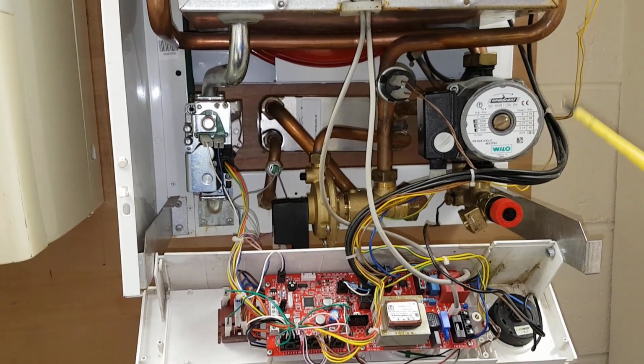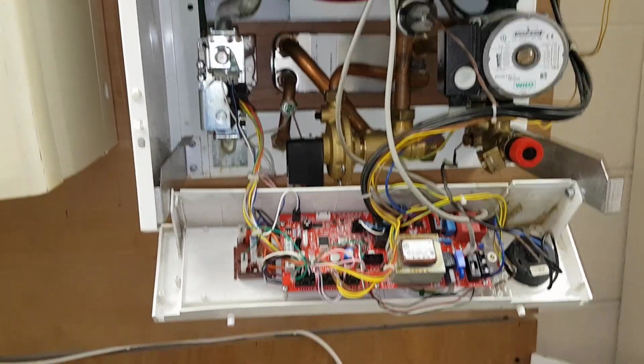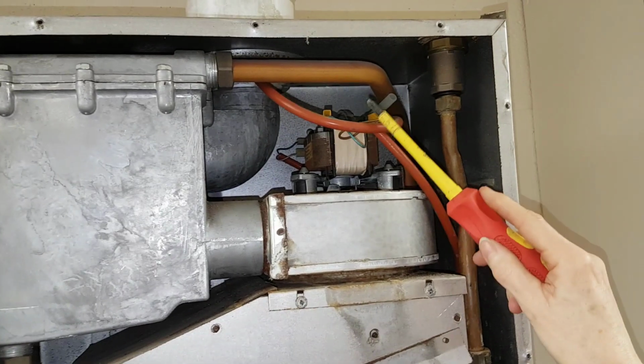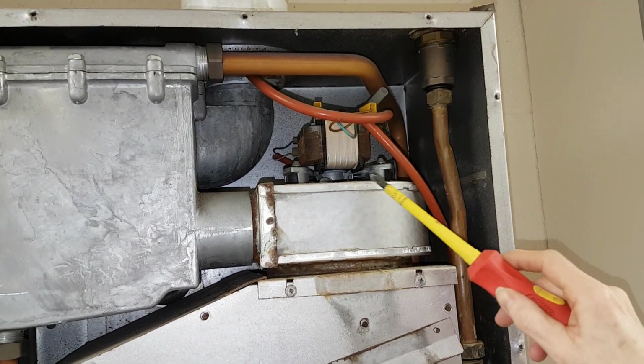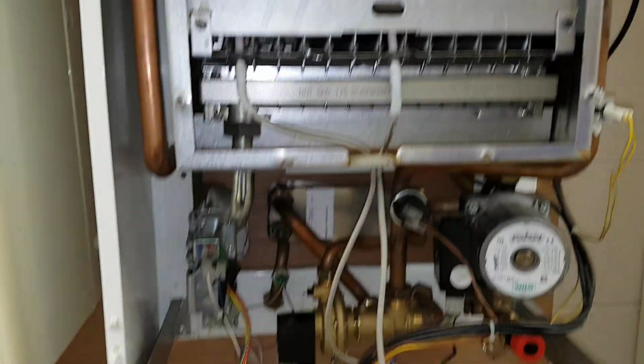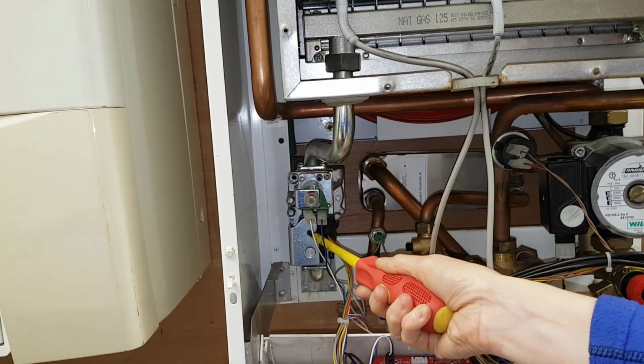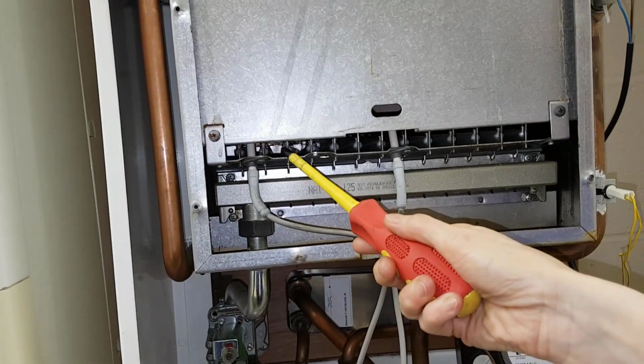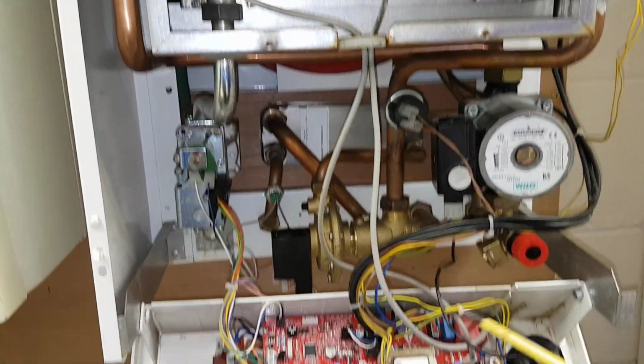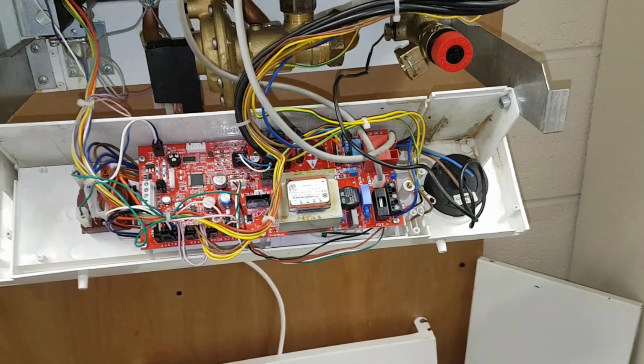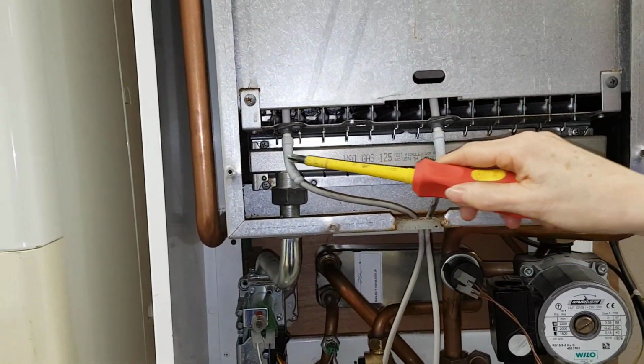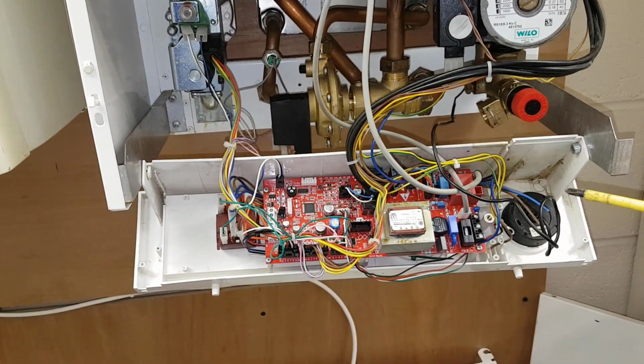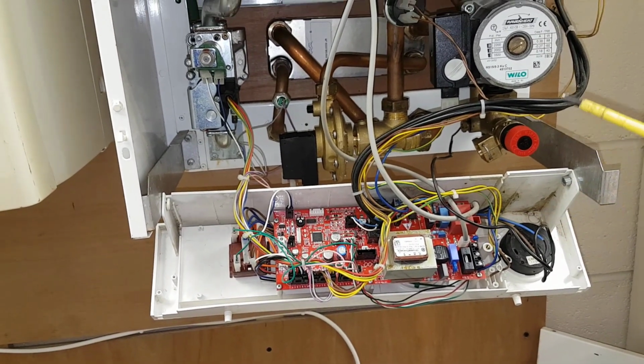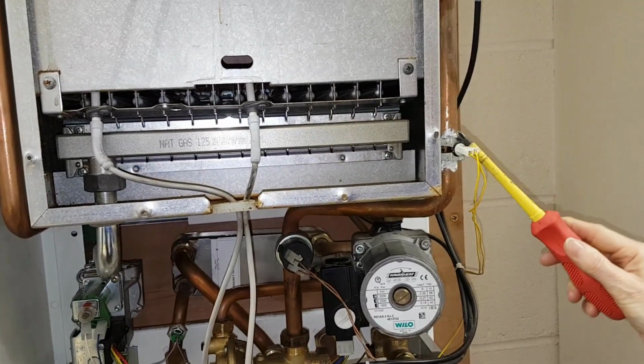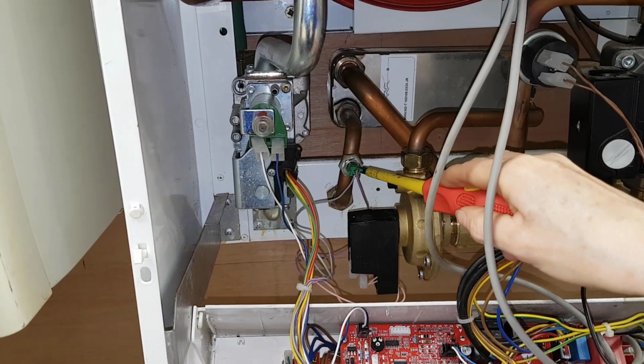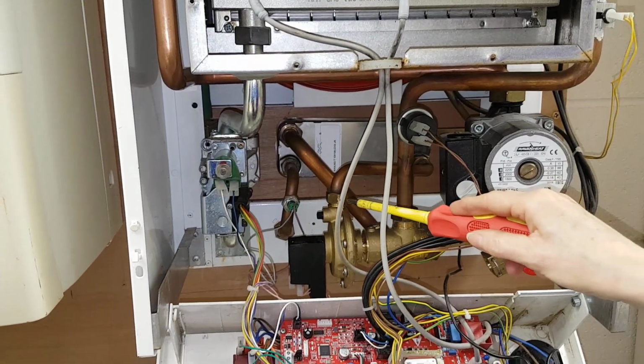Once that starts circulating, it goes back to the PCB, which starts the fan again, and the pressure switch is made. That starts the ignition sequence: it goes back down to the PCB, which energises the gas valve, which allows the gas to come in here to be ignited. It's ignited by this electrode here and the spark generator on the PCB, and then it's sensed by the flame sensing electrode, which goes back to the board. So that completes the cycle. Now, there are two sensors that work in hot water. There's a primary sensor here that has to work, and there's also the hot water sensor that has to work. These two have to work for it to complete its cycle and deliver the hot water.